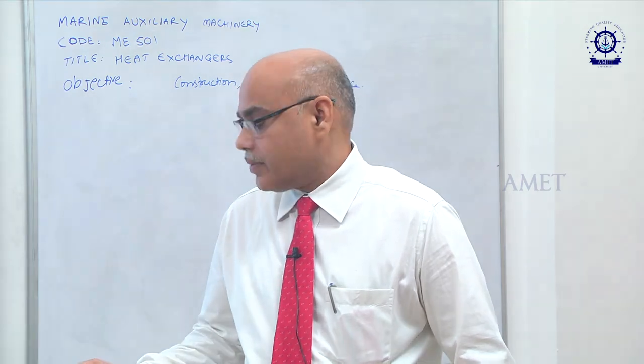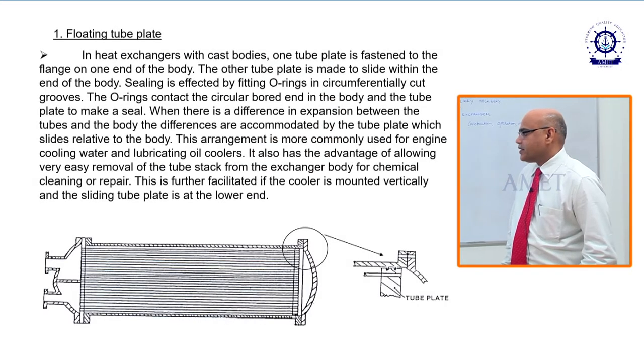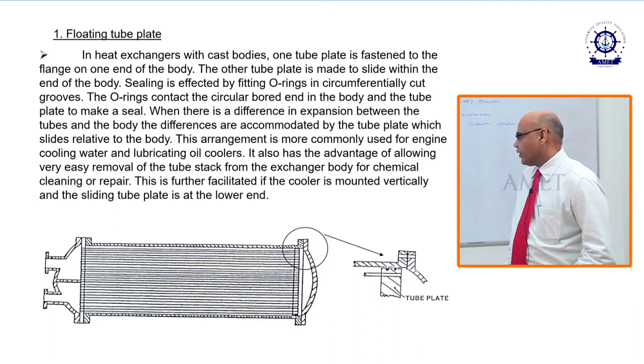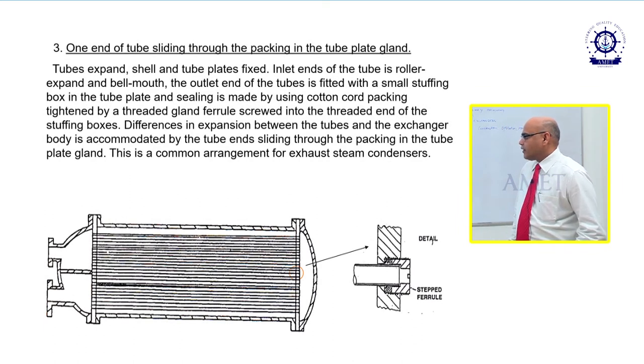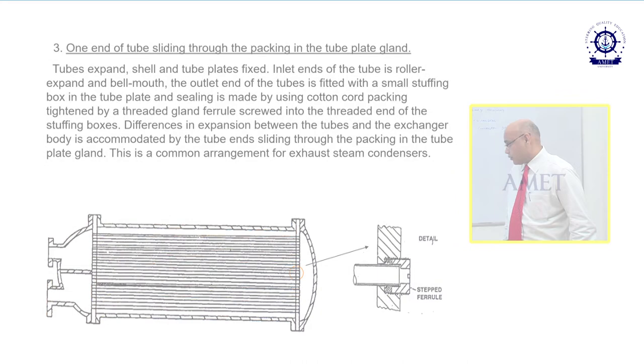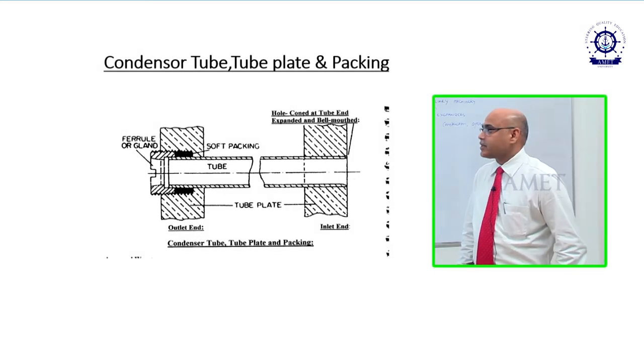In the first arrangement, one side of the tube plate is fixed and the other side is free to float. In the second, both tube plates are fixed but the shell is free to expand. In the third method, one side of the tubes is fixed in the tube plate and the second end the tubes can expand freely in the stuffing box. These are the three methods for handling expansion and contraction of the tubes.